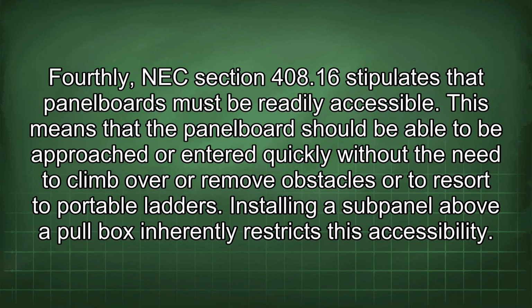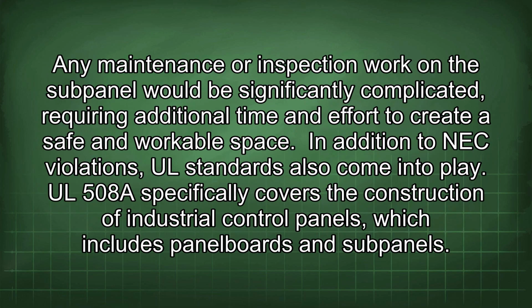Fourthly, NEC Section 408.16 stipulates that panelboards must be readily accessible. This means that the panelboard should be able to be approached or entered quickly without the need to climb over or remove obstacles or to resort to portable ladders. Installing a subpanel above a pull box inherently restricts this accessibility. Any maintenance or inspection work on the subpanel would be significantly complicated, requiring additional time and effort to create a safe and workable space.